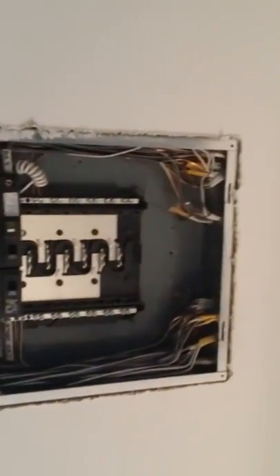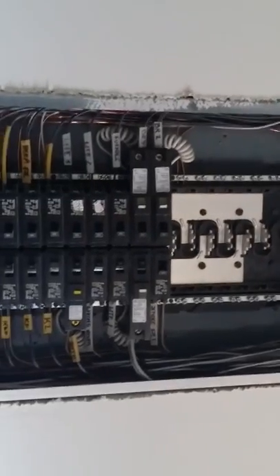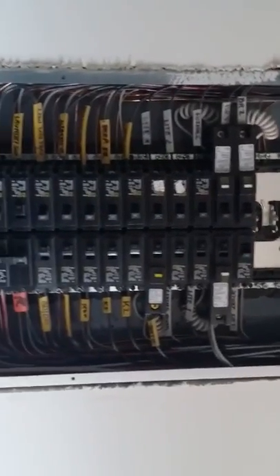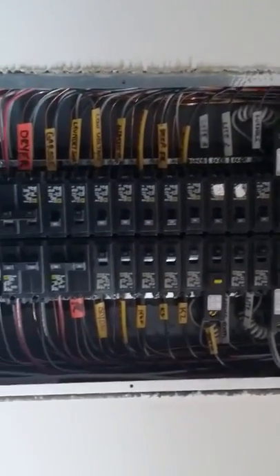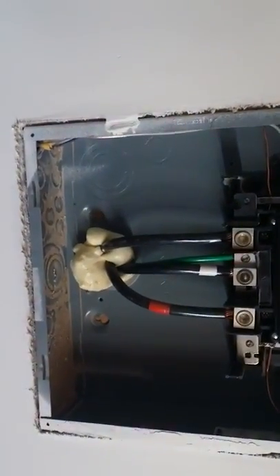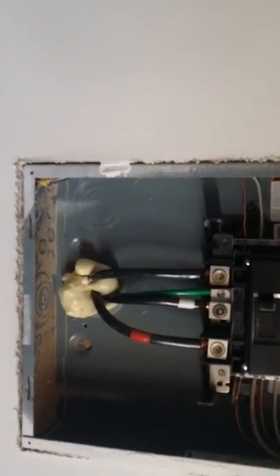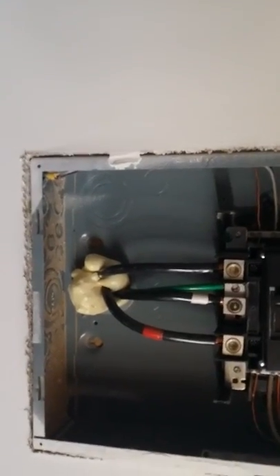Our panel, once again, very nice, neat, clean, tidy. Everything's labeled, clearly identified. We've sealed our port for the conductors. That way, no outside temperature comes in, no condensation in the panel. We'll get all the sawdust and stuff like that out of there.